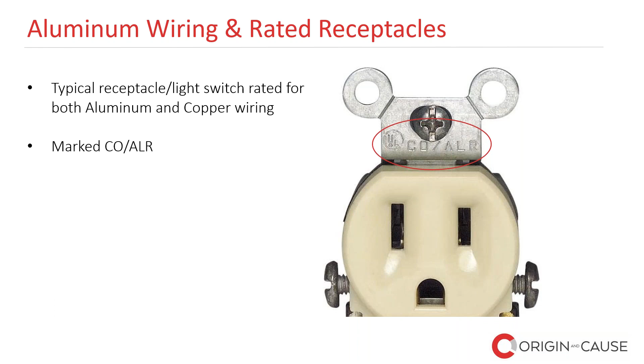And finally, one more case study involving aluminum wiring involved a fire in a home, where there was aluminum wiring to a receptacle that wasn't rated for this wiring, and it was near a headboard and ignited the headboard and resulted in a fire. Now, with further investigation, we identified that this house had aluminum wiring across the home, and there was a heavy load connected to this circuit, which was an AC unit. The receptacle was not rated for aluminum wiring.